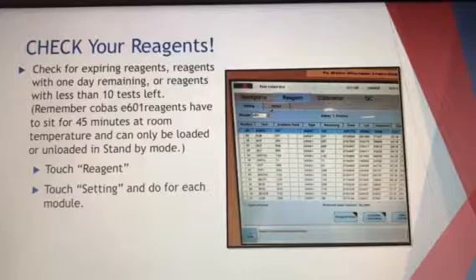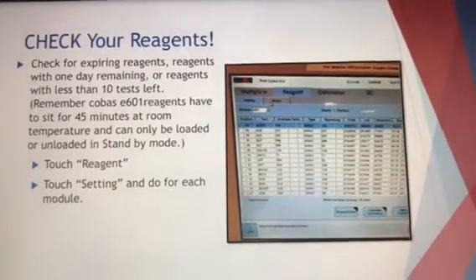Save your coworker some time. If you see it, go ahead and take it off. Or any reagent that has less than 10 tests. Now, for the less than 10 tests, use your best judgment, as I said before. If it's a test that's in a BMP or a CMP, or it's a troponin or a CKMB, something we're doing a lot of, make sure you go ahead and replace them, especially if they're a reagent that's on the 601 side, because you can only replace reagents on the 601 side if the instrument is in the standby mode. So be really, really careful about those.